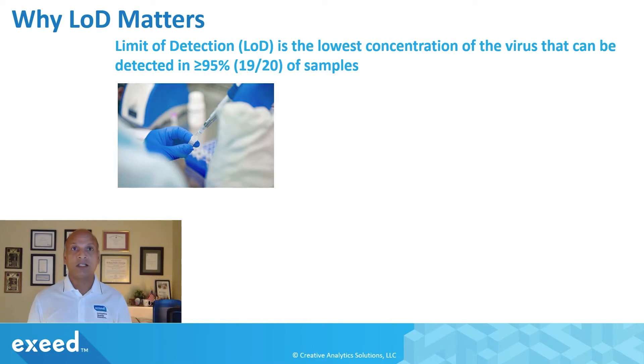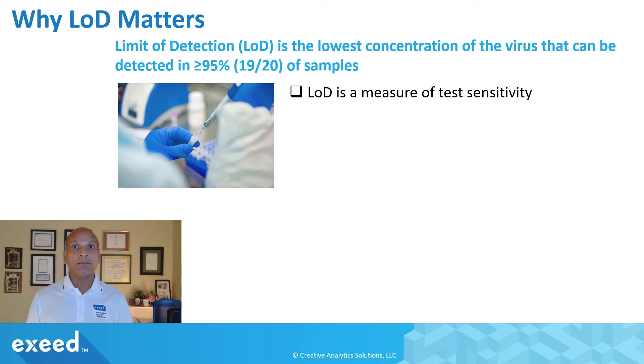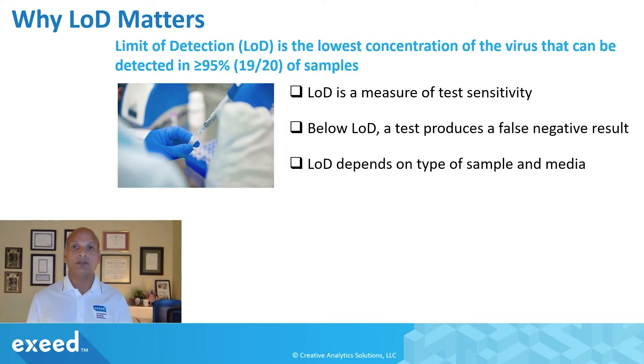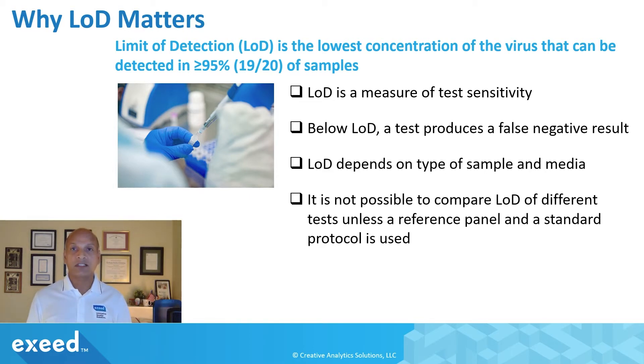Why does LOD matter? The limit of detection is the lowest concentration of the virus that can be detected in greater than or equal to 95% of samples — for example, 19 out of 20 should be detectable if confirmed positive. LOD is a measure of analytical sensitivity, as compared to clinical sensitivity, which is different. Below LOD, a test produces a false negative result. LOD depends on the type of media and sample used, which is why it has been very difficult to compare LOD across different tests.